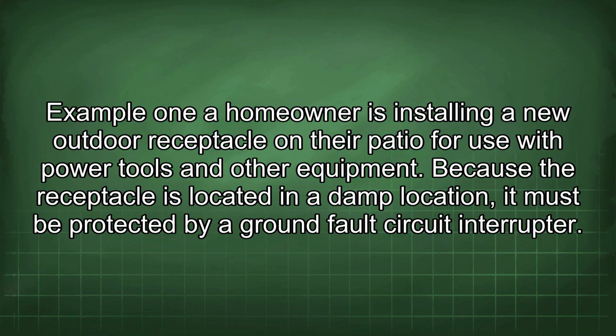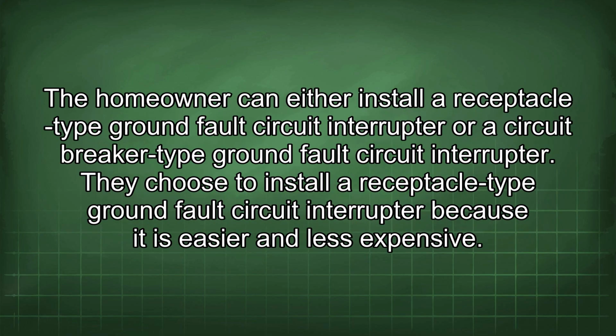A homeowner is installing a new outdoor receptacle on their patio for use with power tools and other equipment. Because the receptacle is located in a damp location, it must be protected by a ground fault circuit interrupter. The homeowner can either install a receptacle-type ground fault circuit interrupter or a circuit breaker-type ground fault circuit interrupter. They choose to install a receptacle-type ground fault circuit interrupter because it is easier and less expensive.